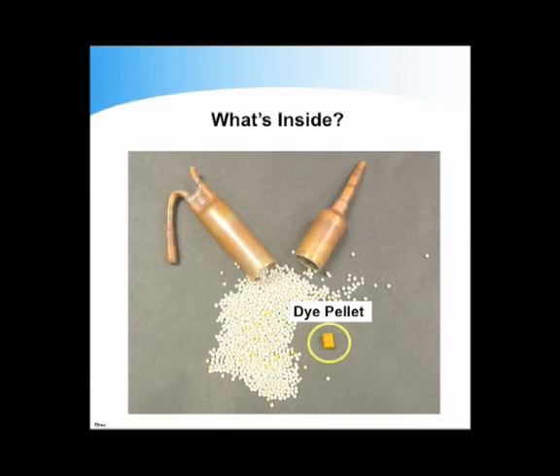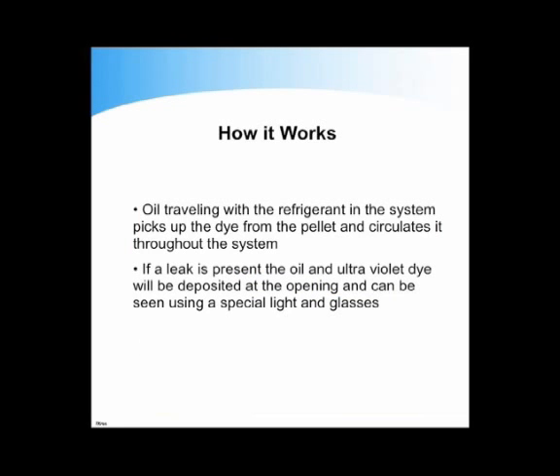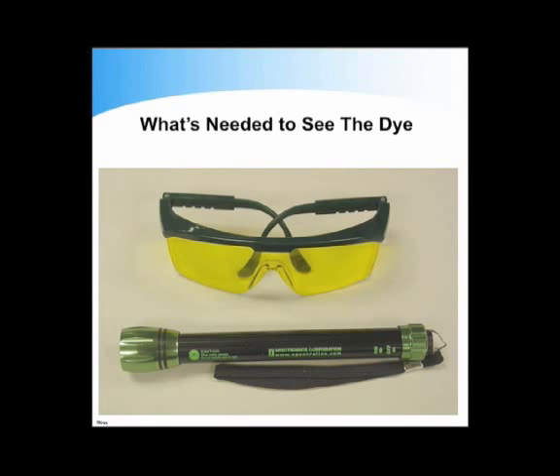What's inside? A small pellet filled with dye is embedded inside the drying agent between two dryer filters. How it works: oil traveling with the refrigerant in the system picks up the dye from the pellet and circulates it throughout the system. If a leak is present, the oil and ultraviolet dye will be deposited at the opening, and it can be seen using a special light and glasses. What's needed to see the dye?